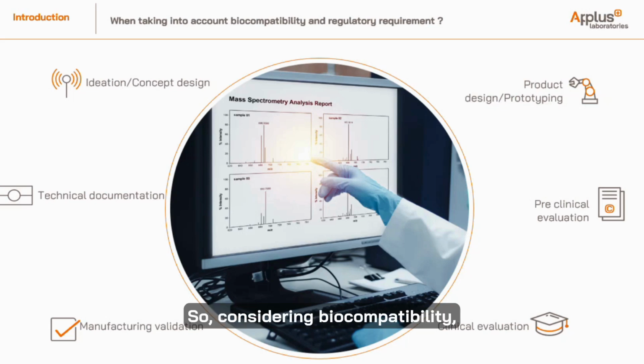So considering biocompatibility is not only a requirement at this stage, but it could also help in the decision and selection of design, materials, and processes to use, as well as appropriate suppliers that are aware of the requirements in medical devices. Once addressed as early as possible, it will really help in the conception and prototyping phase, and then it can be verified during the qualification, and it will be used as input for the technical documentation.